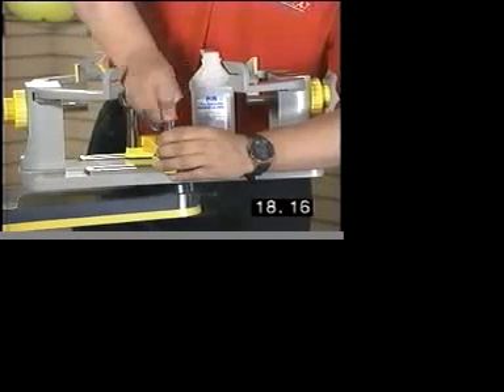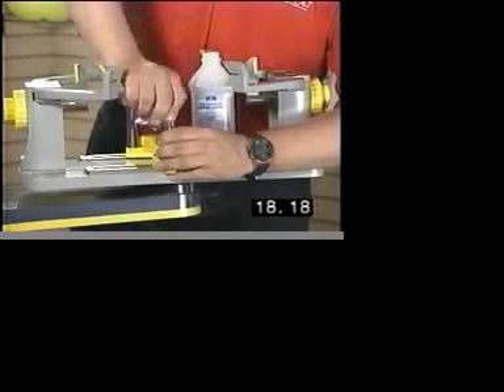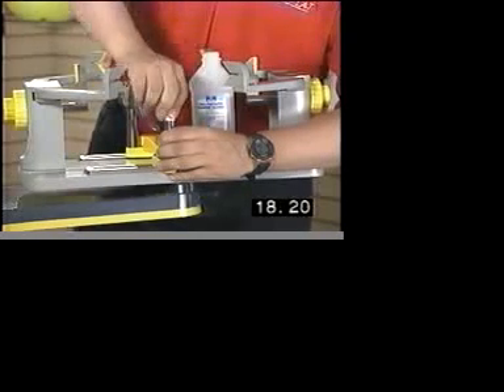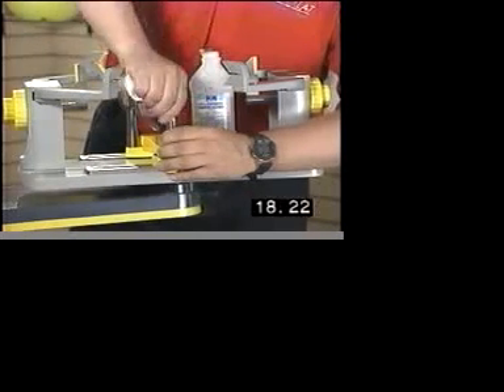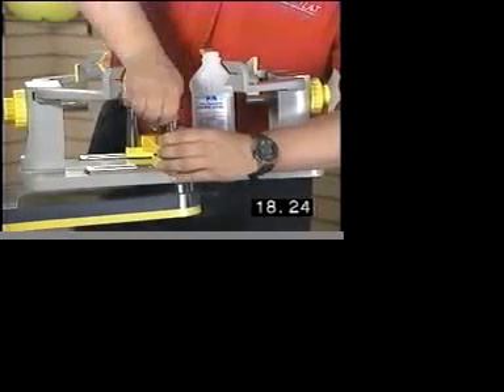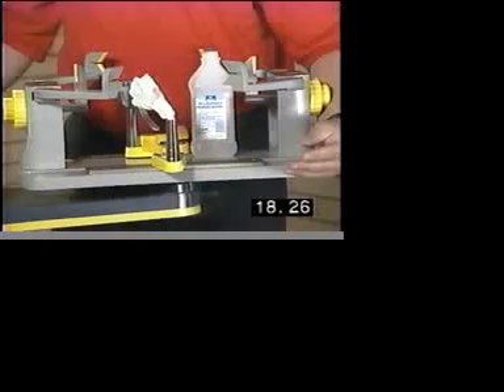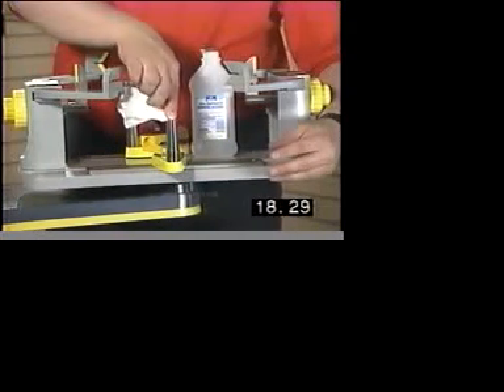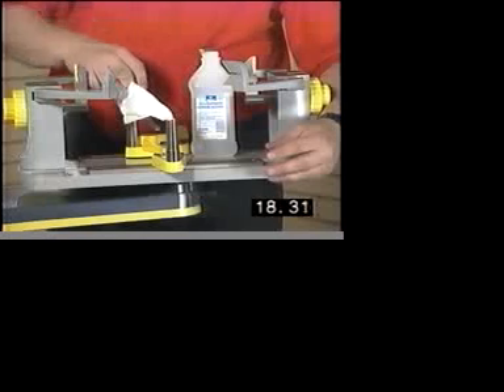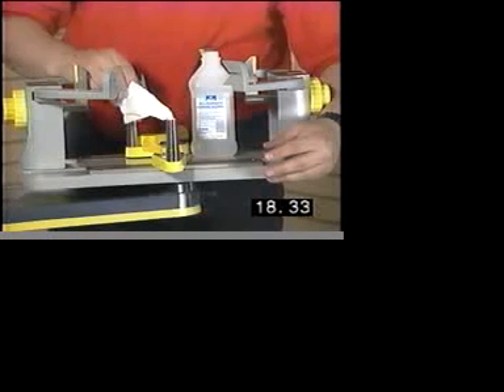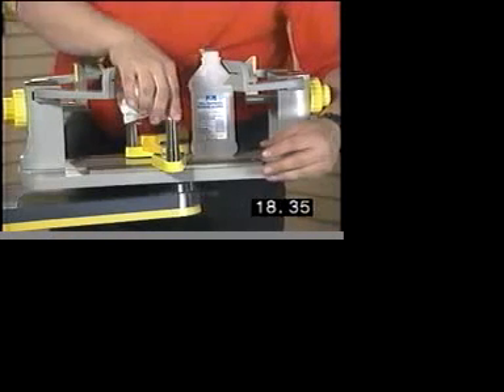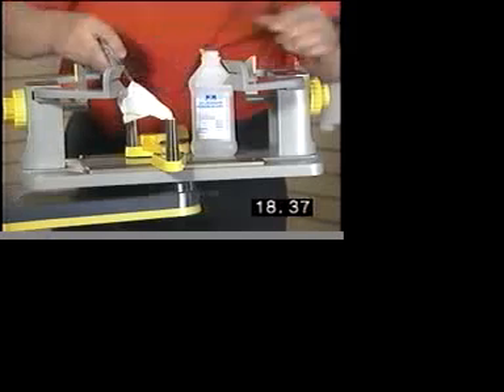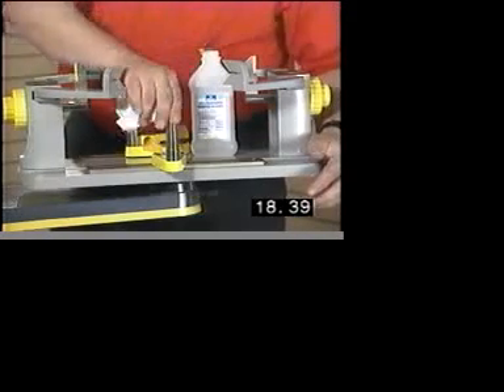Most alcohols do have some sort of water base to them, and they will tend to rust your machine. So you want to make sure you wipe all the alcohol completely off. Never use anything sharp like a screwdriver or an Allen wrench to push this thing through there. If you do mar the insides, these are mic'd very, very carefully, and any tiny scratch on the inside of this or on the outside of your clamp will cause the clamp to stick in the machine permanently.